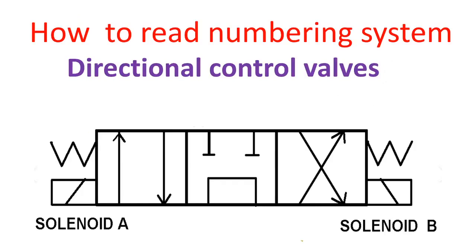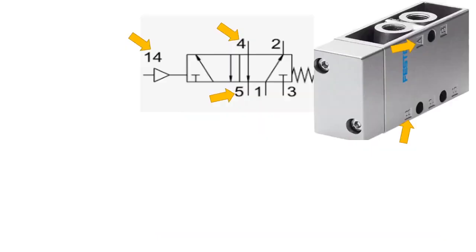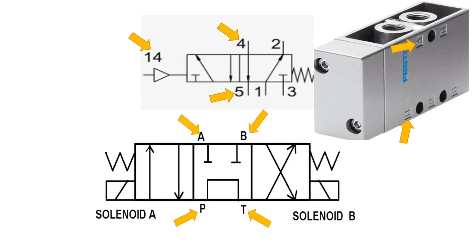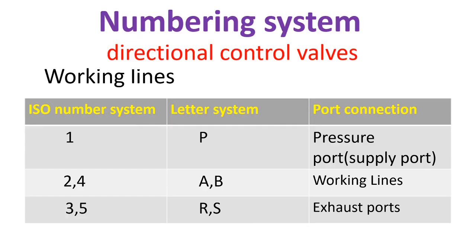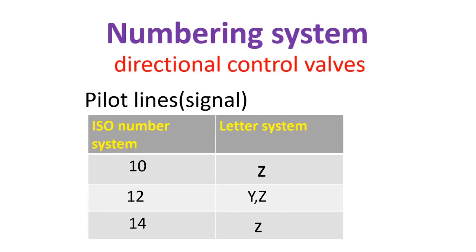The numbering system of directional control valves: number 1 or letter P is the pressure or supply port. Numbers 2 and 4, or letters A and B, are working lines. Numbers 3 and 5, or letters R and S, are exhaust ports. For pilot lines: 10 equals Z, 12 equals Y or Z, and 14 equals Z.